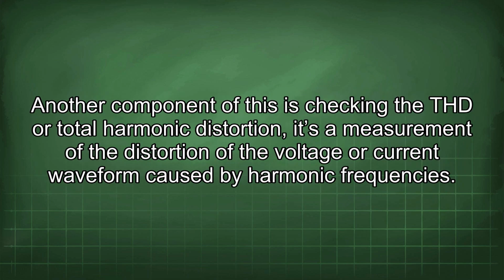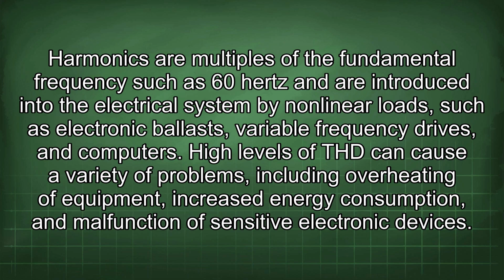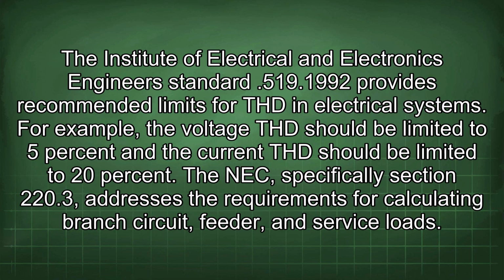Another component of this is checking the THD, or total harmonic distortion. It's a measurement of the distortion of the voltage or current waveform caused by harmonic frequencies. Harmonics are multiples of the fundamental frequency, such as 60 Hz, and are introduced into the electrical system by nonlinear loads such as electronic ballasts, variable frequency drives, and computers. High levels of THD can cause a variety of problems, including overheating of equipment, increased energy consumption, and malfunction of sensitive electronic devices.